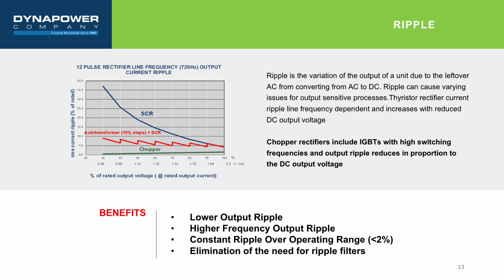When the output voltage decreases from rated value in thyristor rectifiers, the AC ripple content increases. The output ripple for a 6-pulse operating system is 360 Hz, 720 Hz for a 12-pulse, and 1440 Hz for a 24-pulse system. At the same time, chopper rectifiers' ripple content is constant and not dependent on the circuit type. Therefore, the output voltage variation does not increase the ripple content. Chopper rectifiers include IGBTs with high switching frequencies, resulting in lower output ripple, higher frequency output ripple, constant ripple over the operating range, less than 1 to 2%, and elimination of the need for ripple filters.